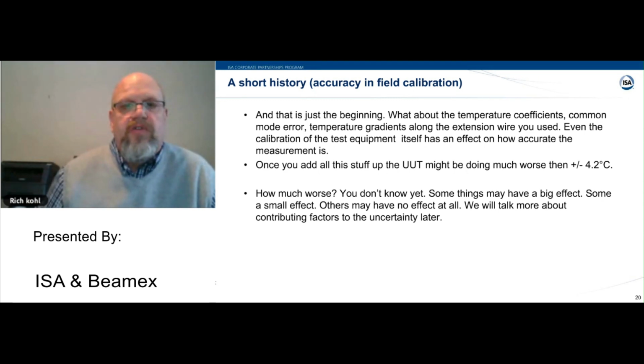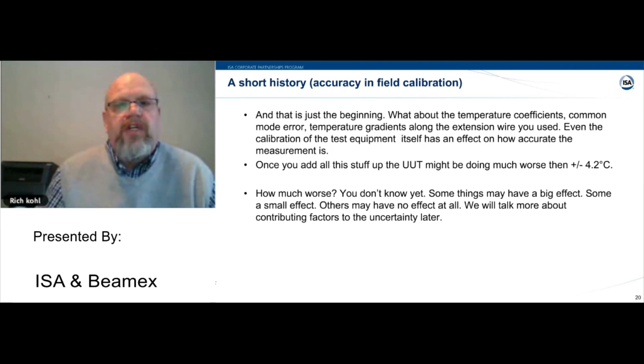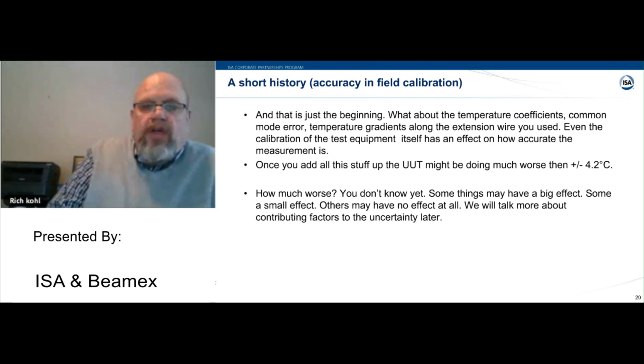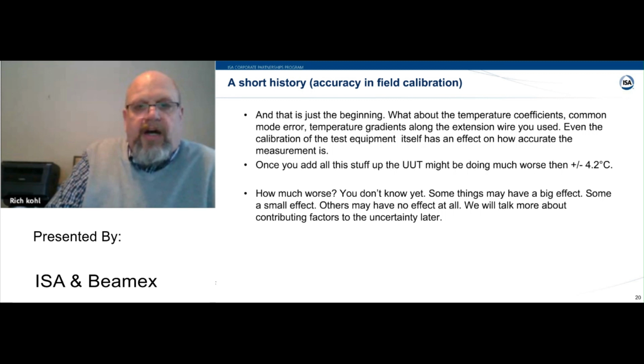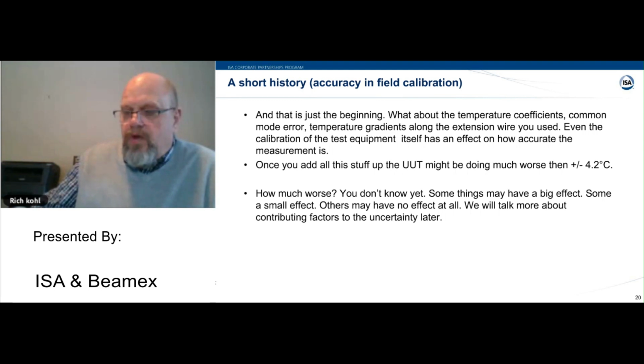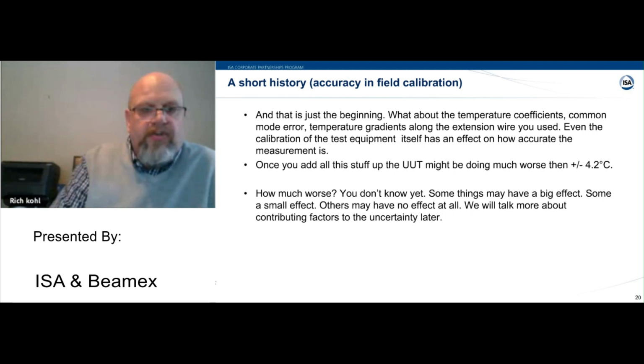There's a bunch of other contributing factors that need to be considered when you're looking at total uncertainty. We have temperature coefficients, common mode error, and temperature gradients along extension wire, if you're using extension wire. Even the calibration of the test equipment itself has an effect on how accurate your measurement is. Once you add up all this stuff, your actual UUT might be measuring much worse than 4.2 degrees C. How much worse, we really don't know at this point. You have to calculate it all out, and before you can do that, you have to understand your calibration and your test equipment to find out what's really going on with your measurement.